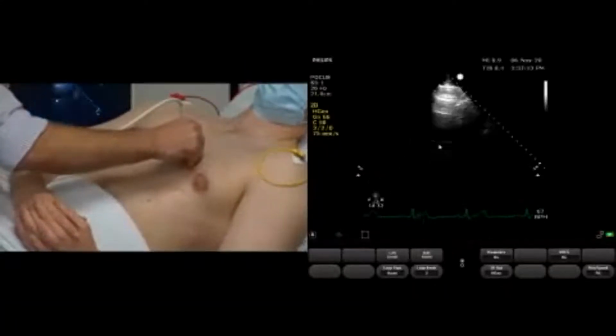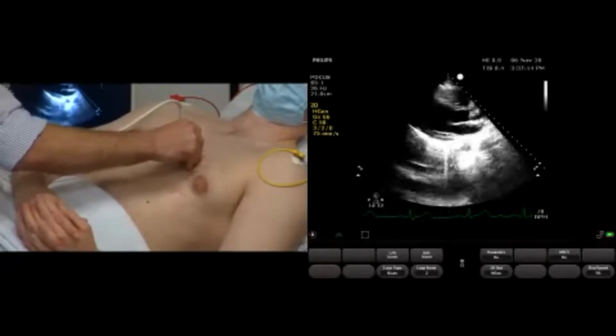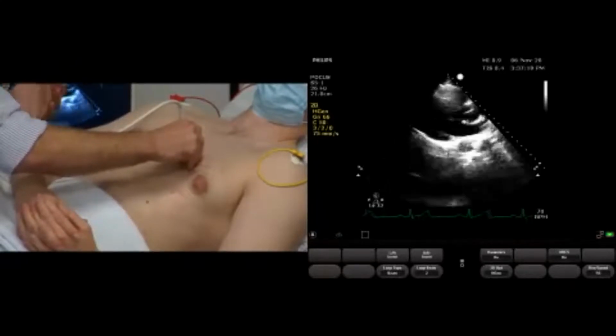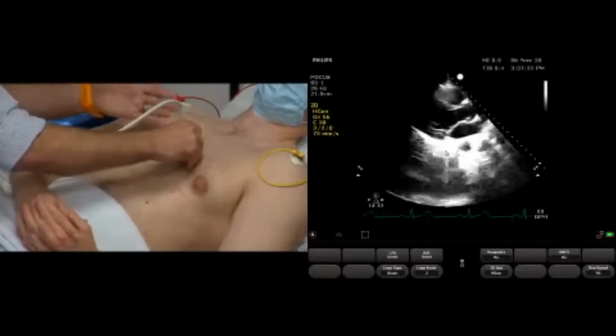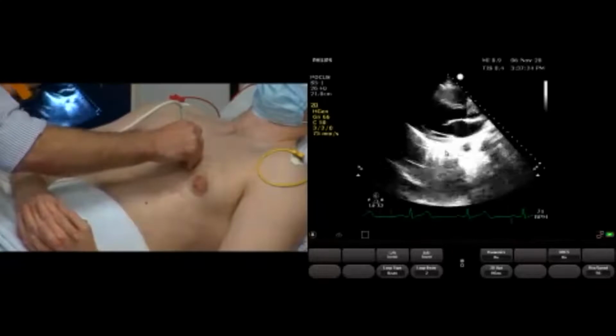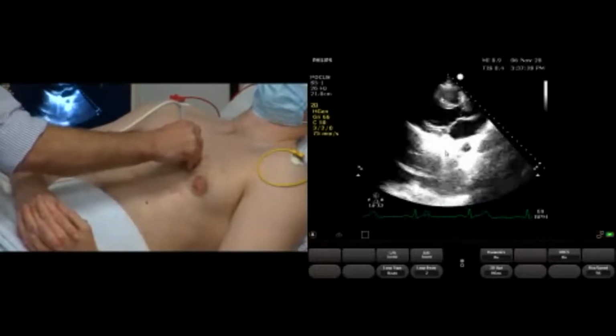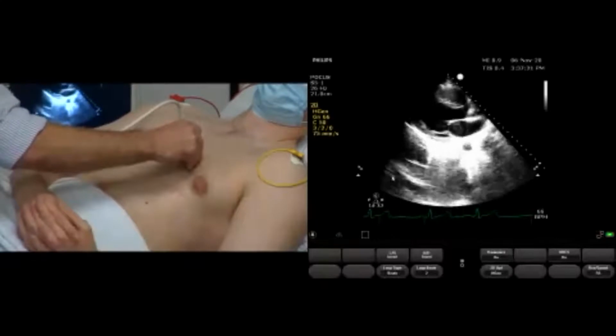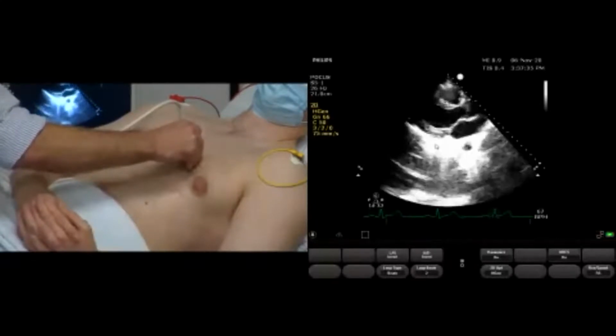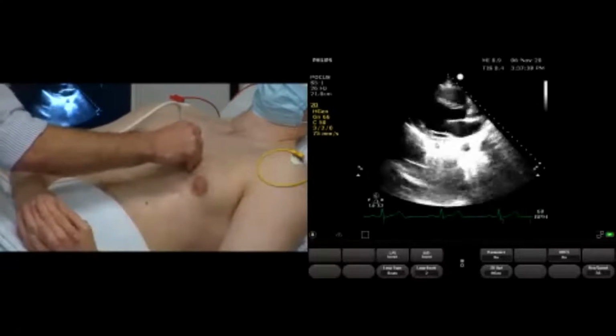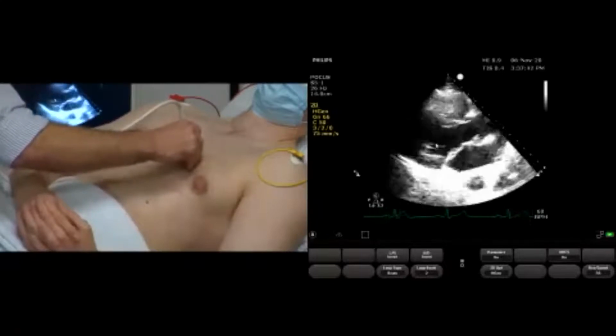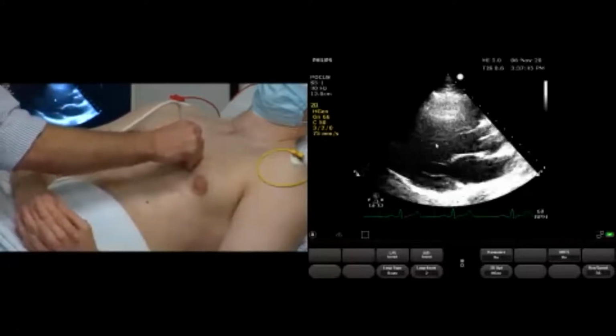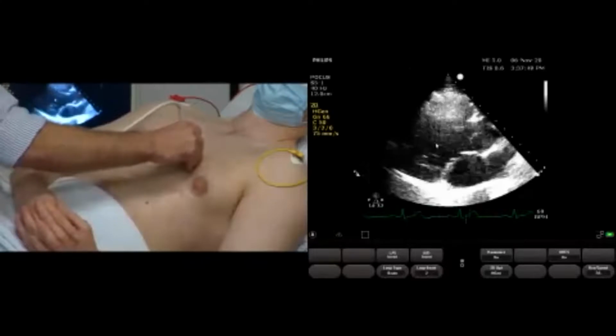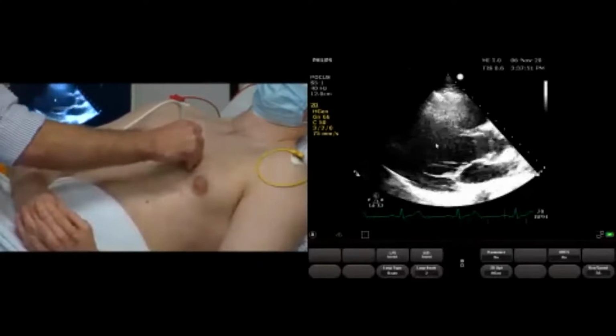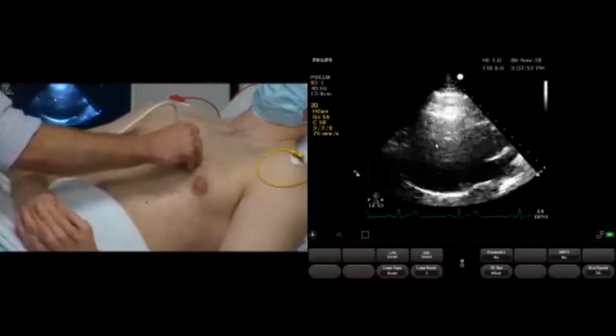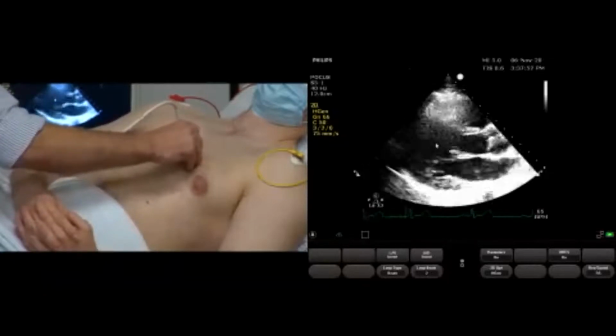What's happened is that you've got a very strong reflector in your pericardium, and that sets up a reverberation signal between the pericardium and the transducer itself. The transducer detects the extra reverberations as being twice the distance of where they actually come from, so you create a second heart at a depth below that pericardium. To improve that, I'm going to change my depth. There are a number of benefits to this: you remove that ghost image, plus your frame rate improves, which allows a better image and greater clarity of detail when you're examining the patient.